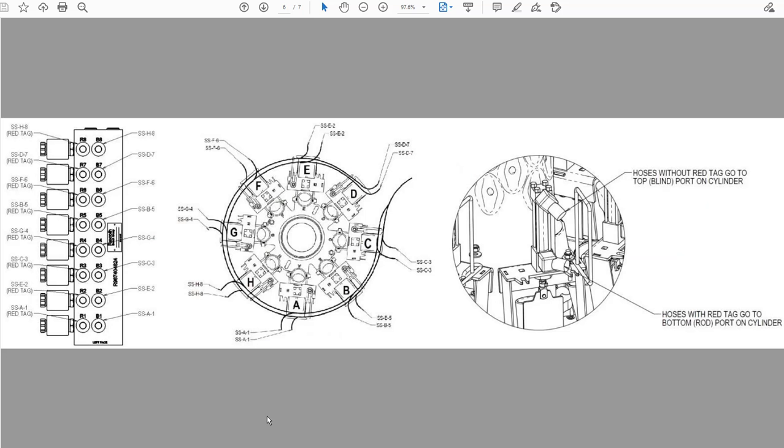Off of the ASCP valve block, the hoses are connected to the R and B ports going out to the knife valves. The R ports are connected to the rod end of the cylinders and marked with a red tag at each end. The B ports are connected to the blank end of the cylinder. All the lines are labeled to which section they go to and then the red tags differentiate which end of the cylinder they go to.